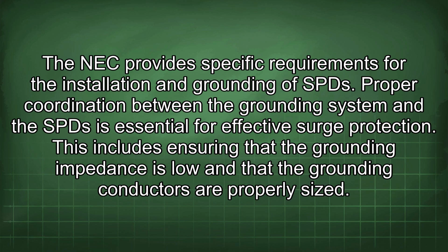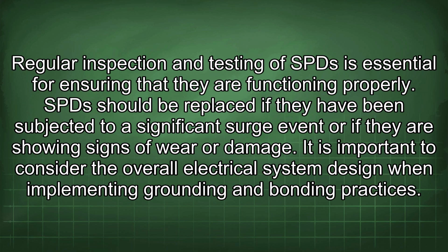Proper coordination between the grounding system and the SPD is essential for effective surge protection. This includes ensuring that the grounding impedance is low and that the grounding conductors are properly sized. Regular inspection and testing of SPDs is essential for ensuring that they are functioning properly.